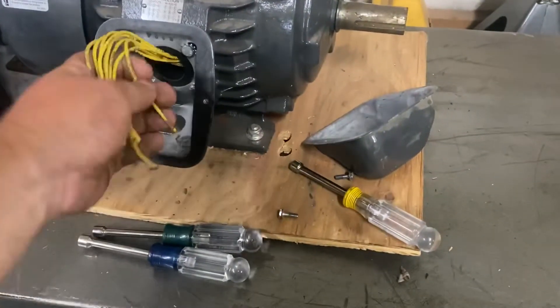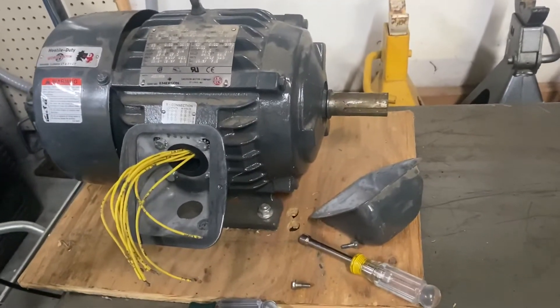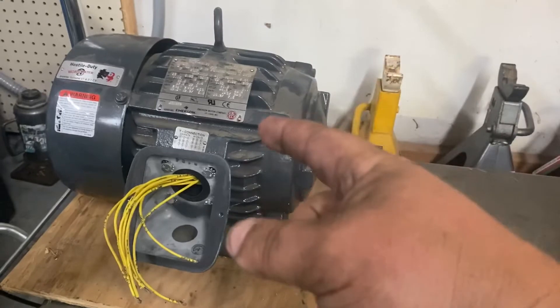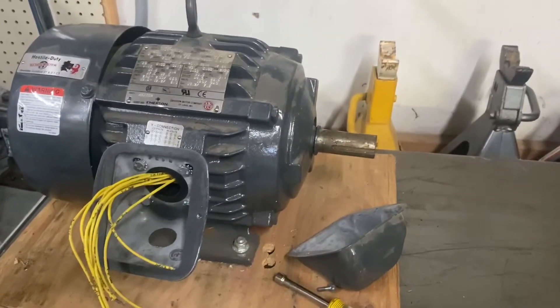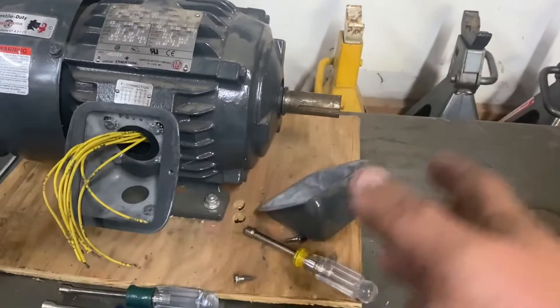When you run your wire from the motor, don't just stick stuff through here and run bare wires. Follow electrical codes and put stuff in flexible conduit if you're allowed to. Make sure the motor is mounted solidly wherever it is. That shaft is going to be spinning the whole time this motor is generating power — be mindful of that. I like to make metal guards like those used between pumps and motors in waterworks. Make sure nothing can come in contact with the shaft when it's spinning.